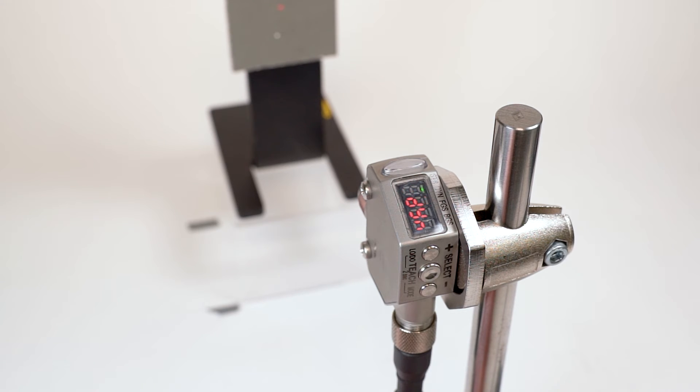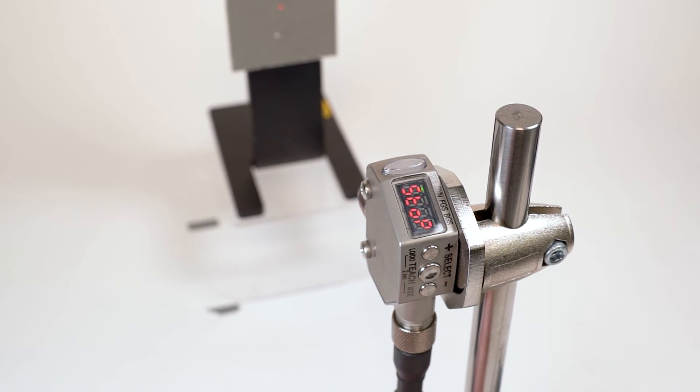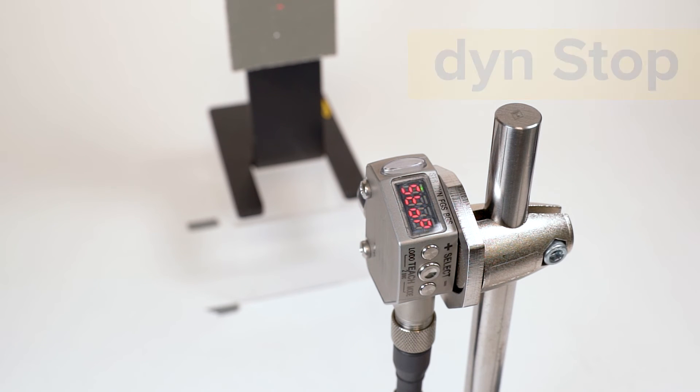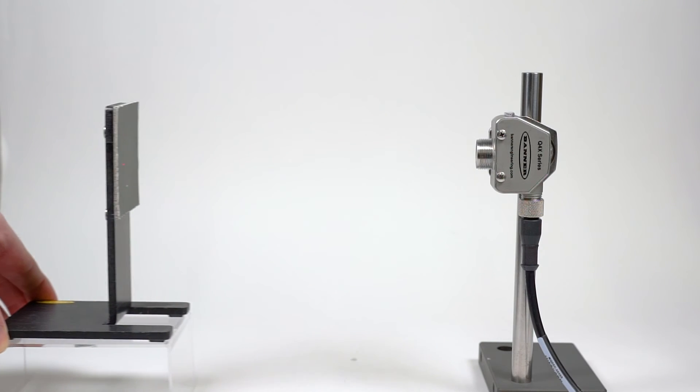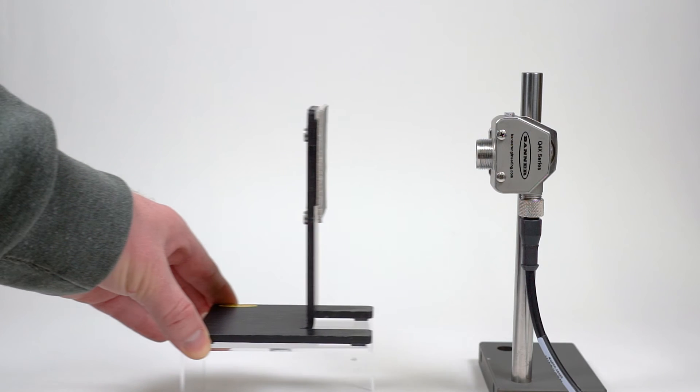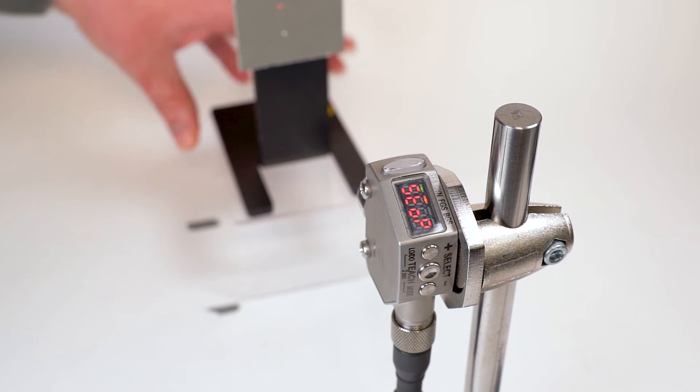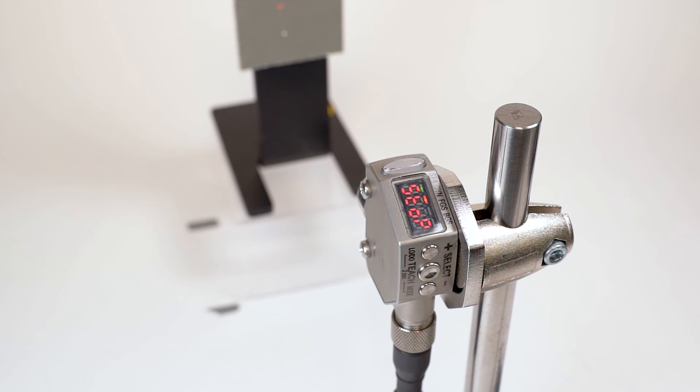Press the teach or select button to begin. The display will show DYN stop. Present multiple on and off conditions to the sensor. After presenting several target conditions, press the teach button again.